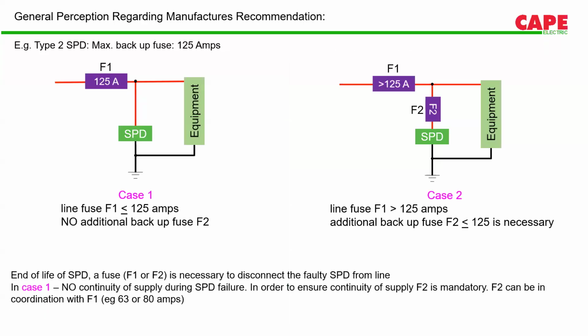If you see this case, in case number 1, when the SPD fails, F1 blows out. That means supply is cut off. So whenever the SPD is blown or failed, the supply to equipment is cut off. That means the equipment is always protected. Once the SPD fails, the protection goes and the equipment supply also disconnects. Whereas in the second case, whenever the SPD fails, only F2 blows. That means the supply continues to the equipment. So we get continuity of supply in case number 2.